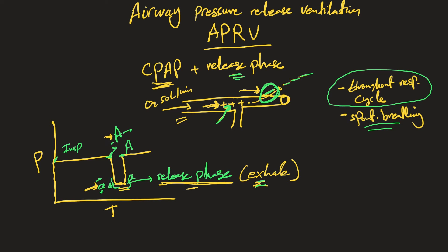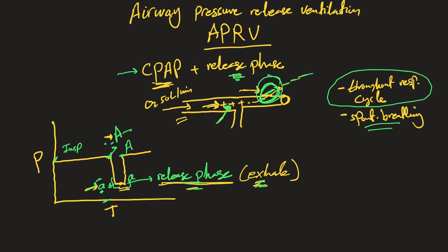To wrap up: airway pressure release ventilation is CPAP plus a release phase. The release phase is when the valve is open and pressure drops from capital A to small A, creating a pressure gradient that allows air to be exhaled. The longer the release phase, the more exhalation occurs. We must be careful not to let small A drop to zero, because that would cause alveolar collapse, de-recruitment, and hypoxia — which is not the purpose of APRV.